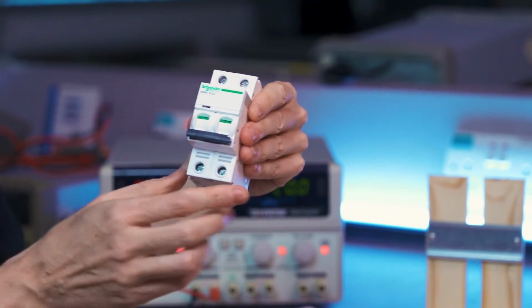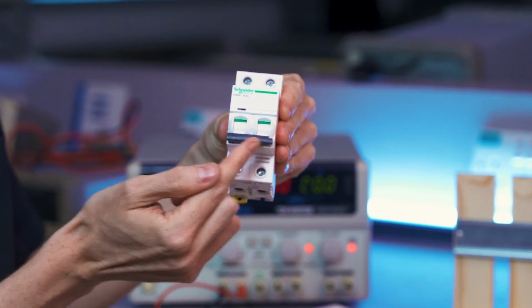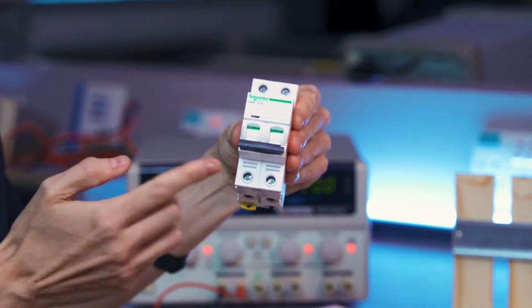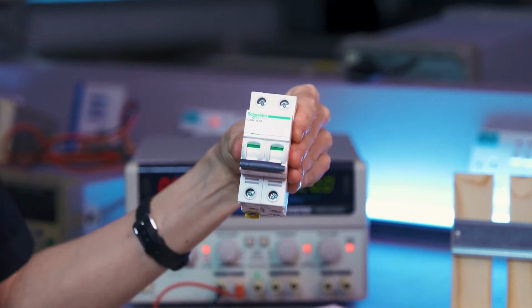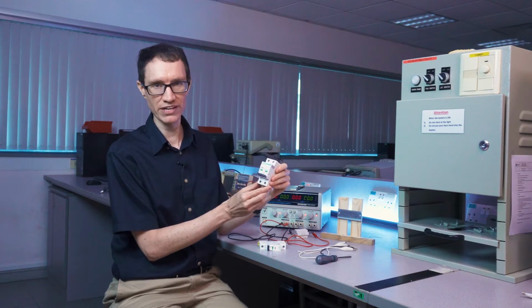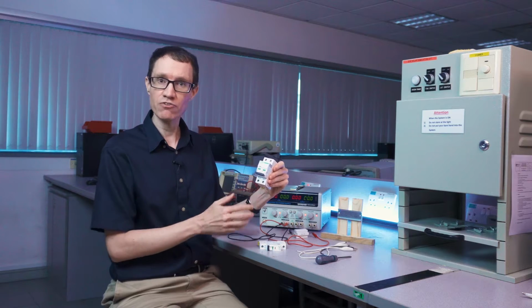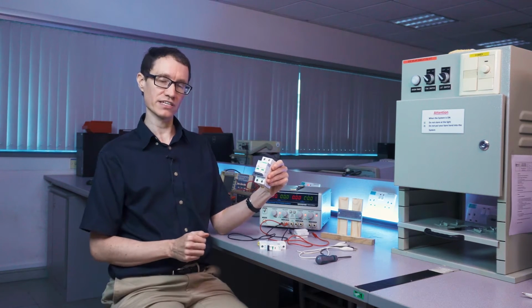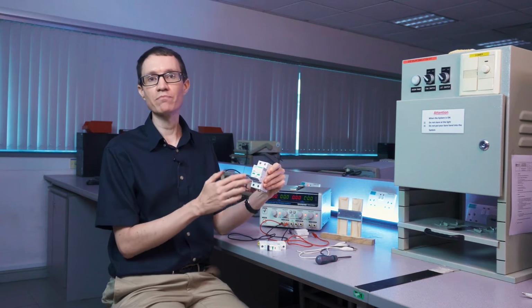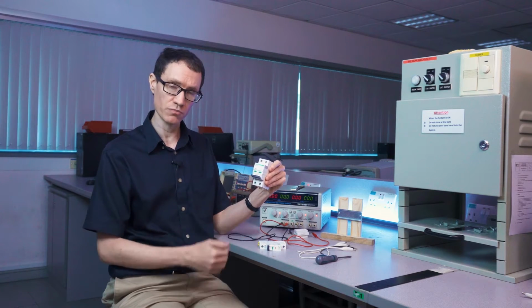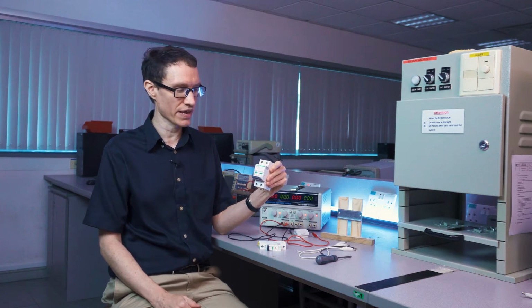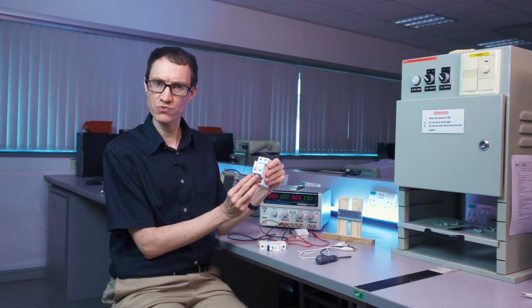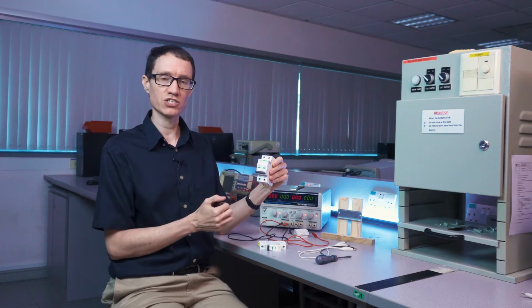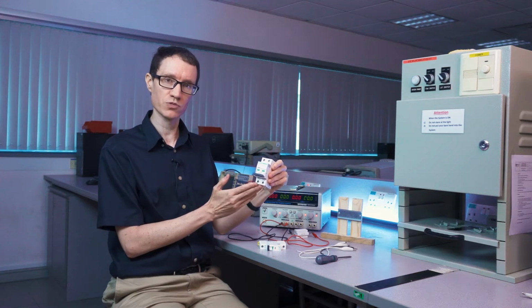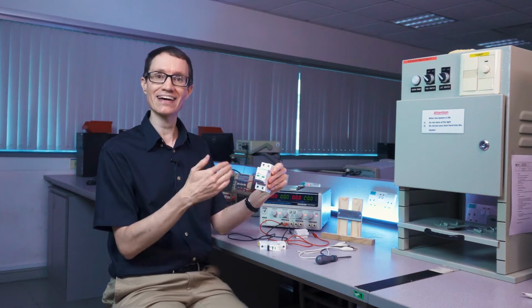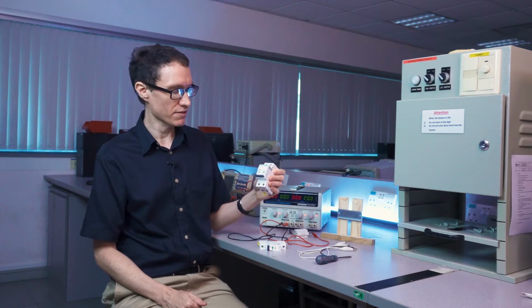In the 2-pole circuit breaker, we have two switches that are bonded together here, so that if one side of the breaker trips, then the other side is going to trip too. A 2-pole circuit breaker is often used as a main switch. For example, in a house, you would have electricity coming into this circuit breaker and then branch off into other 1-pole circuit breakers, which would then feed circuits throughout the house. Now, the reason it has two switches rather than just one at the main switch is because this circuit breaker is capable of switching off the neutral side and the hot side simultaneously if there's a problem.